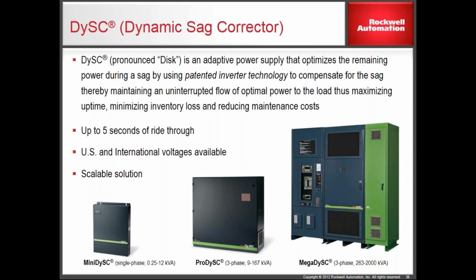On the 3-phase world, we call it ProDySC or MegaDySC. We kind of divided the line. The ProDySC describes products that go from 25 amps to 200 amps, okay? So here we're looking at a 50 amp product. It's got an interface on it. You can go back and call back the events. You can see what happened. And that 50 amp device would be about this wide, this thick, and about this high. Right? As they get bigger, 200 amp looks like a small refrigerator. Right? This is a 400 amp, and at the 400 amp level, we call them MegaDySCs. They go 4, 8, 12, 16 on up.